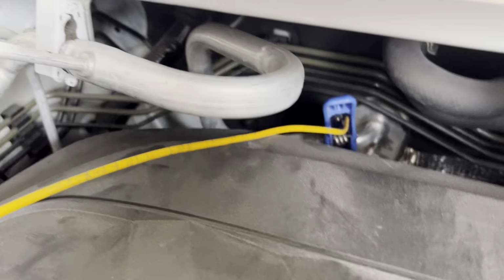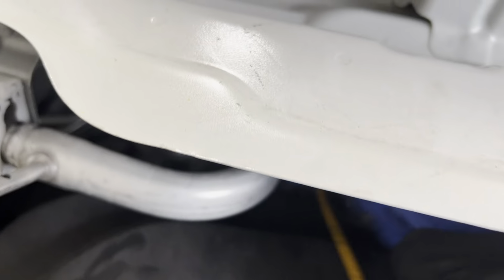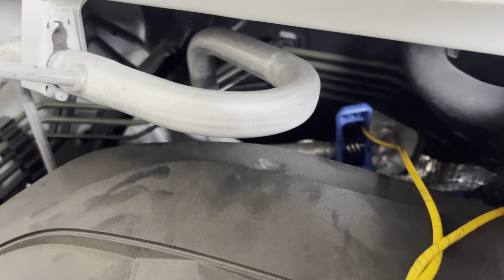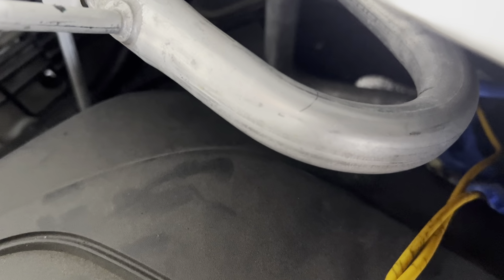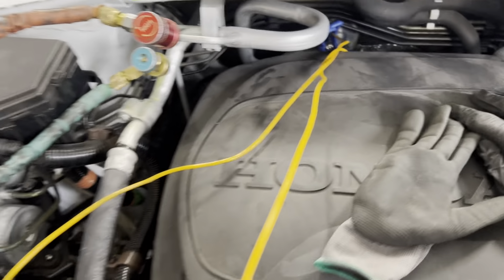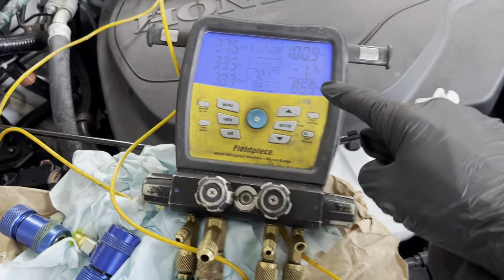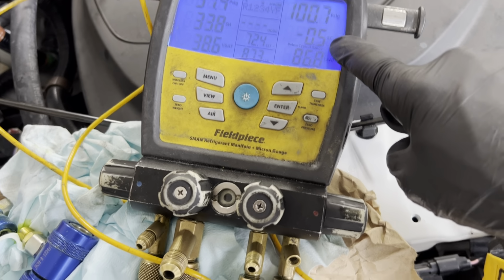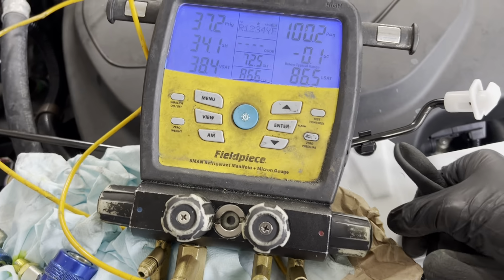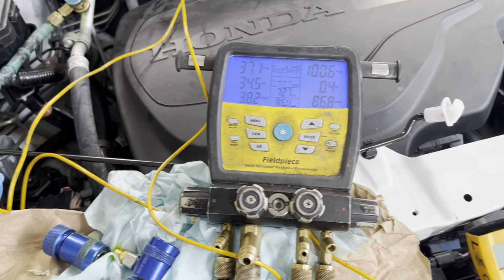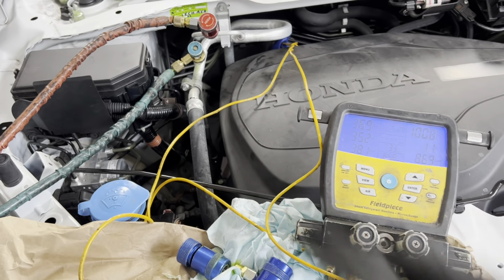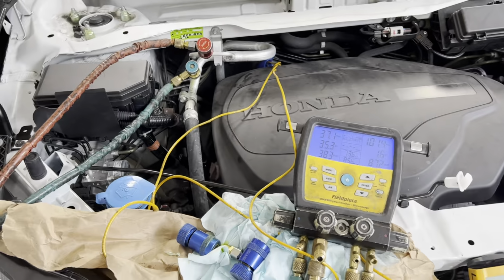Okay, can I get to the other side? Now, I want to take this and I want to put it on the line coming out. There we go. It's cool. I am now on the liquid line coming out of the internal heat exchanger. Now look at our subcooling. Well, it didn't change much, but it changed a little bit. Negative. Supposedly you can't have negative, but that's the job of the internal heat exchanger, to cool down the liquid refrigerant before it goes inside.